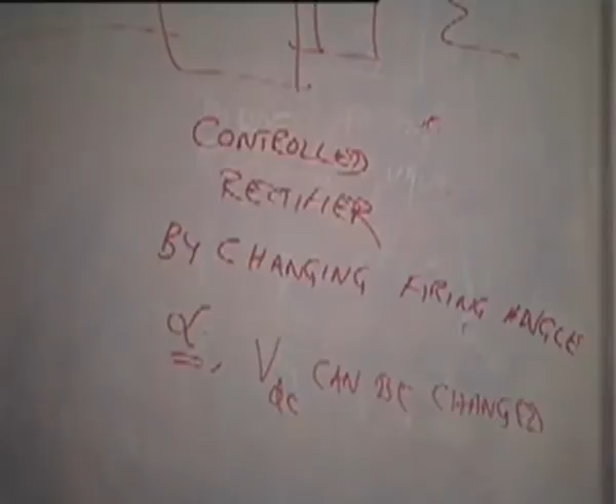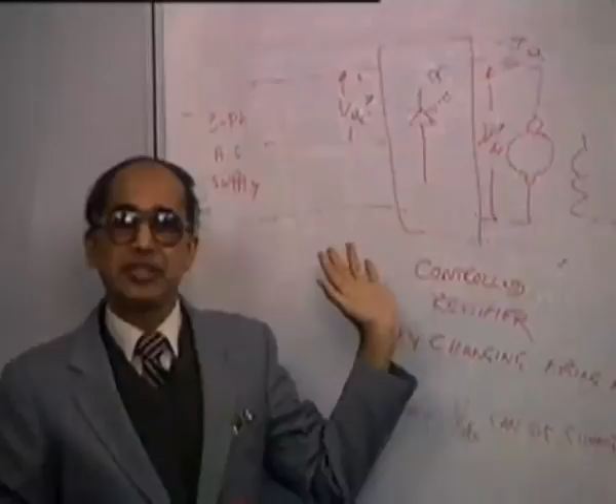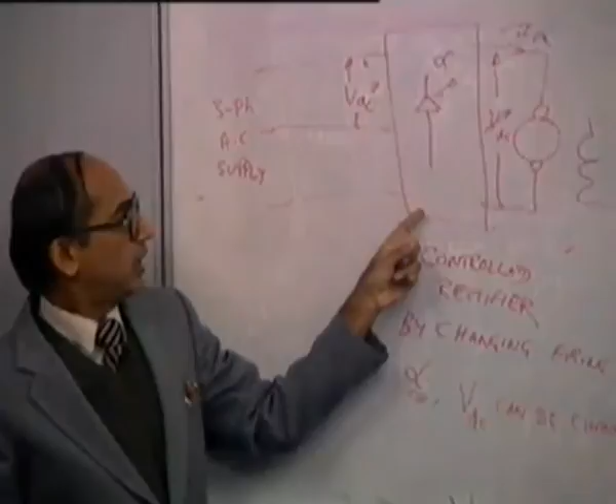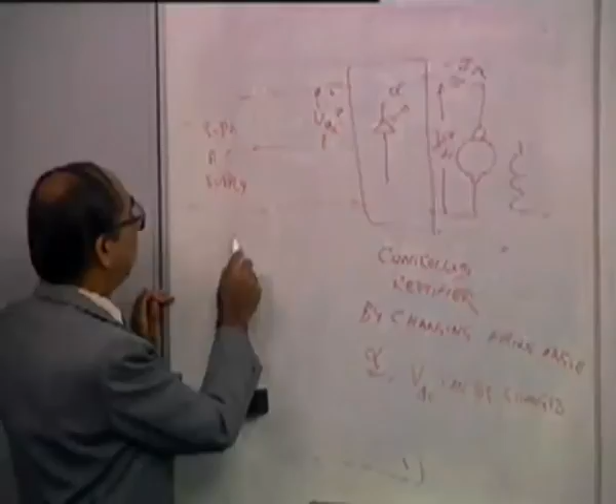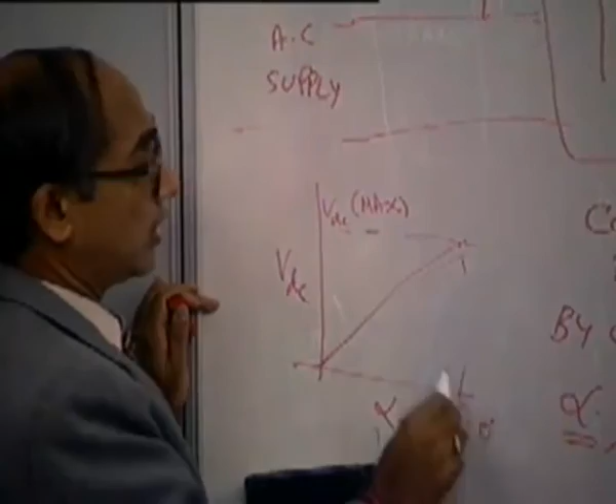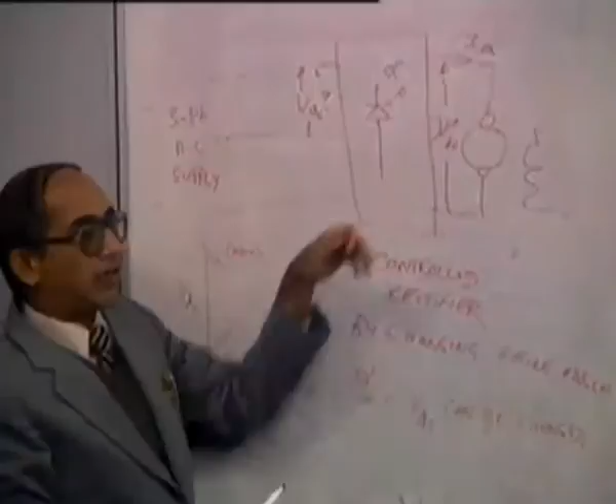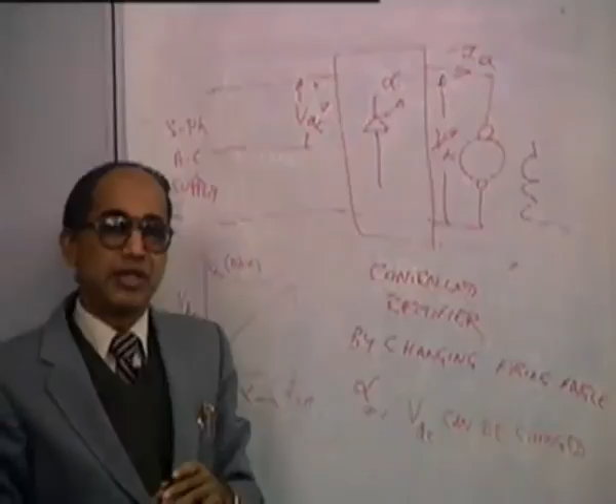This is another feature of the starting methods. Presently most of the DC drives have this starting method. All you have to do is to slowly change alpha, the firing angle of the thyristor converter bridge, and increase the VDC. So VDC will have a variation with reference to alpha. You can vary from 0 to whatever is the full maximum value, and ultimately when alpha is 0 degrees, there is maximum possible conduction. So this is the second way of changing the VDC.